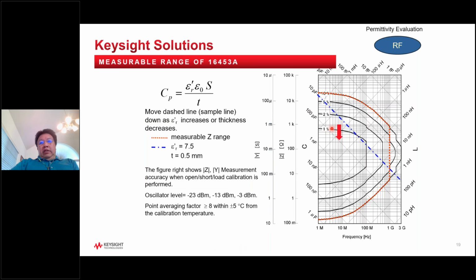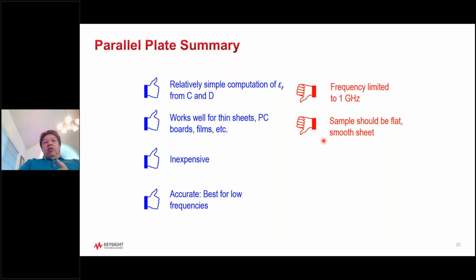The same scenario here. Yeah, it has a measurement zone. I wouldn't go into details. So what is good, what is bad about these low frequency parallel plates? Relatively simple computation. As you can see, the formula works well with thin sheet, the PC board film. Inexpensive, of course, depends on your point of view, and it's best for low frequency. The limitation, as I mentioned, is that it stops at 1 gigahertz, and the sample has to be a flat and smooth sheet.